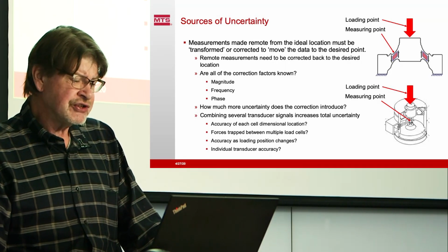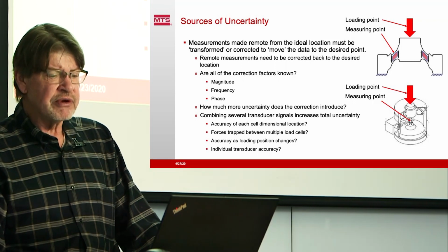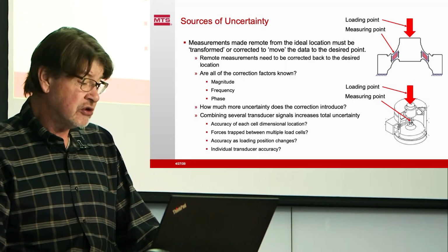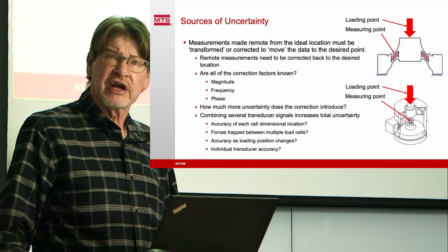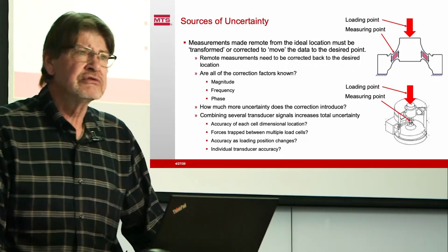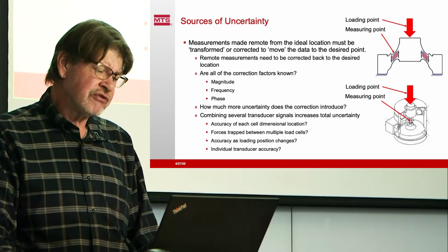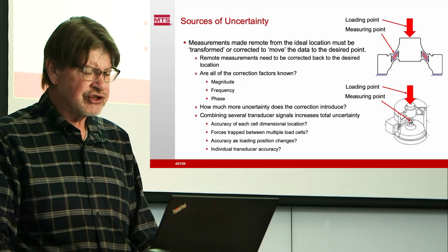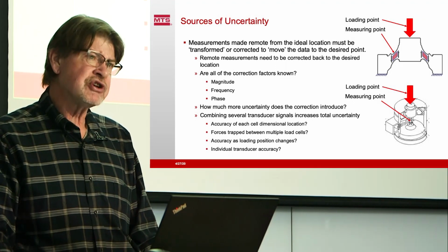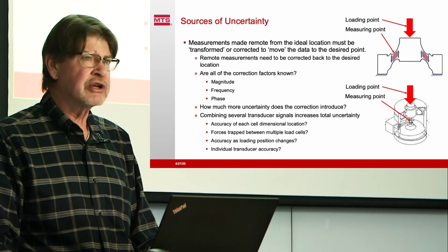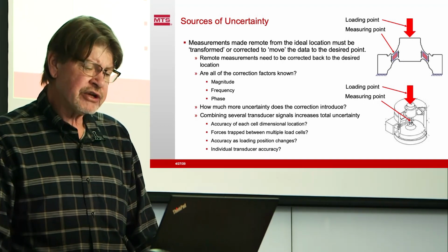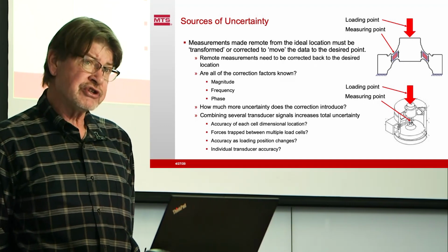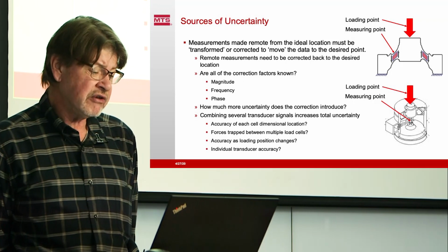How much uncertainty does this correction introduce? So when we move the data back to the face of the load cell, what are the sources of error for that? Mass, inertial loading, deformation. Combining several transducer signals increases the total uncertainty. Let's say we want to sum three or four load transducers together to get a reading. How accurately are they located? Do we know exactly where they are? To what level of accuracy?